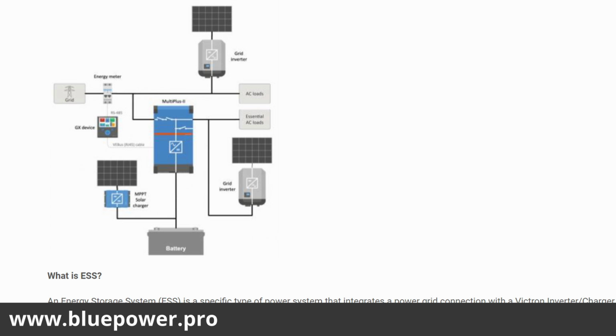And then we've got the grid tie inverter on the output side that's AC coupled. So with the energy meter installed on the input, we can achieve zero feed-in limitation from both of our grid tied inverters in this situation. We can feed excess PV power to our AC loads, our non-essential loads. So we can have the geyser connected over there, and all our bigger loads connected on the input side, and still feed it from solar power.